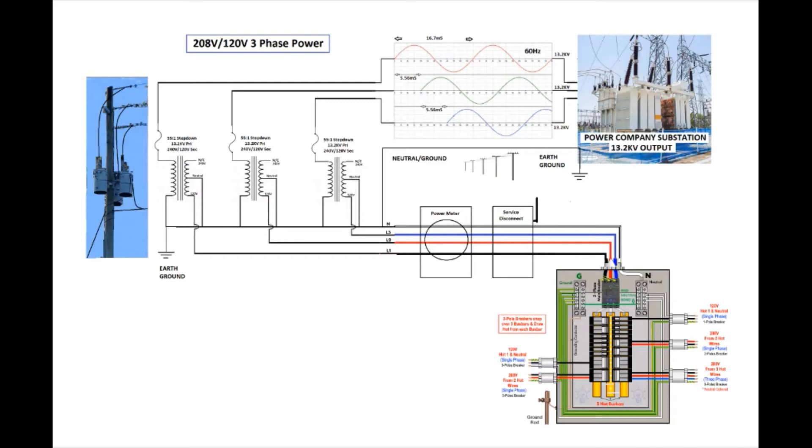I also want to do an actual demonstration using an oscilloscope. One of the biggest mysteries was that no one ever seemed to address where L1 originates from — whether the power company officially designates a wire as L1 with some kind of marking. There's no indication of any kind of markings anywhere. And all the testing procedures always talked about having L2 and L3 backwards, but no one talked about whether we're sure we have the right L1.